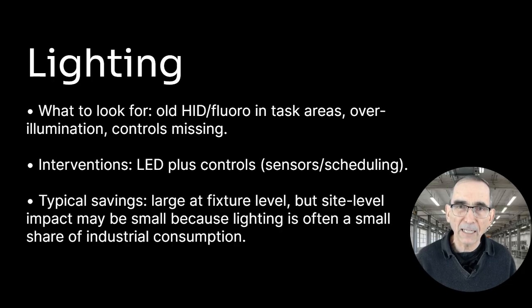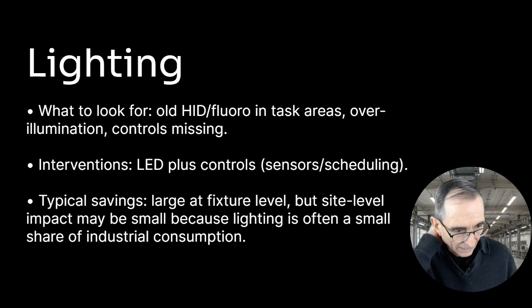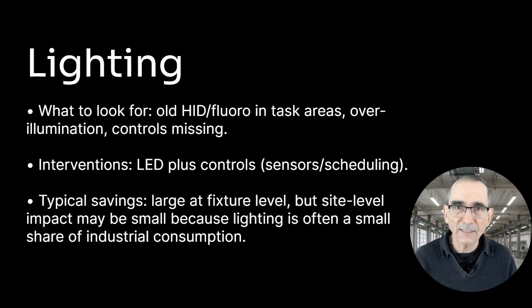And the interventions can be LED lighting plus controls, noting that LEDs ain't LEDs. There's different qualities of LEDs and there needs to be some effort put in the specification of the LEDs. The typical savings are actually very large at a fixture level, but site level impacts may be small because lighting is often a small share of the industrial consumption.